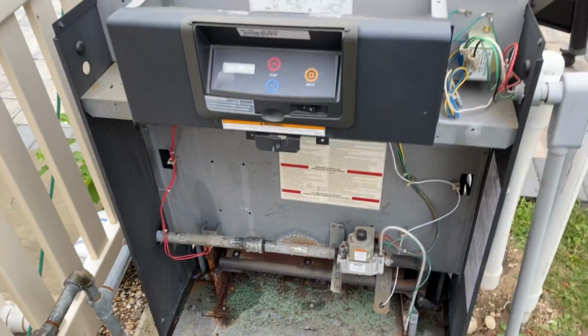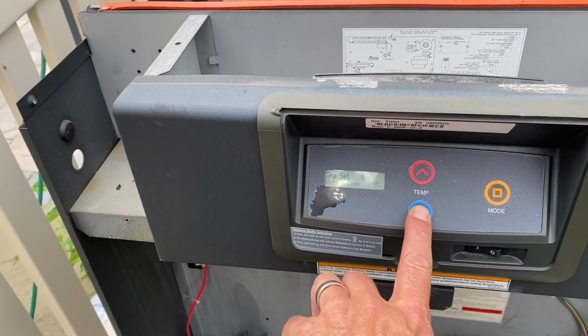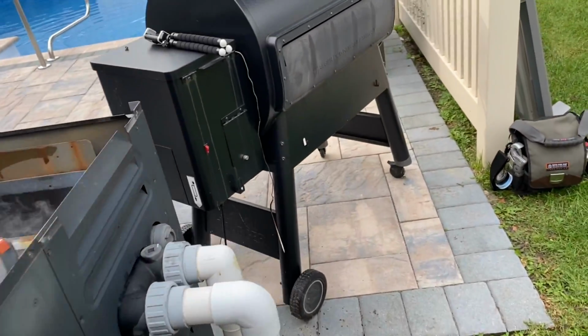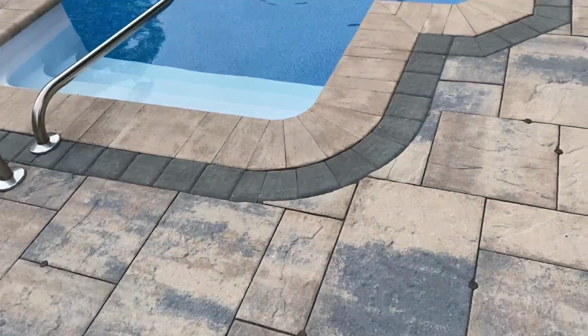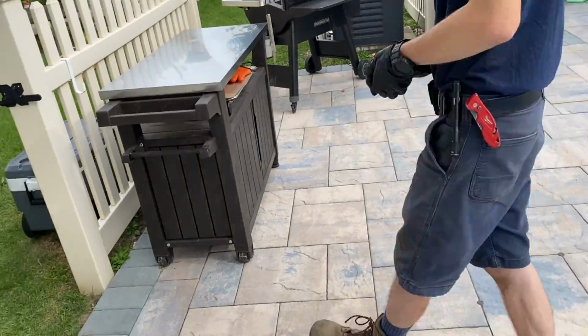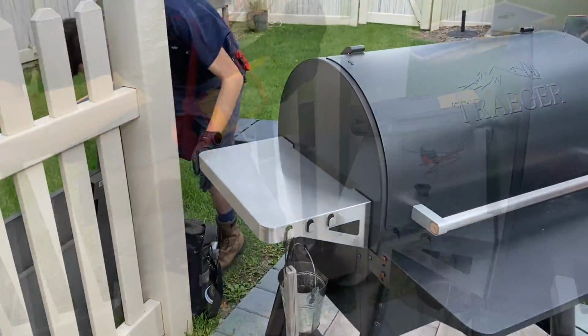So we're good for now. Let's lower the temperature. It's 75. Let's feel the water. How important is the temperature difference? By the end of the day, he'll be warmer. It's 400,000 BTUs. Yeah, that's nice and warm. Matter of fact, let's get the Fluke. All right, and let's put the thermocouple on there, and let's see what the temperature is of the outlet.